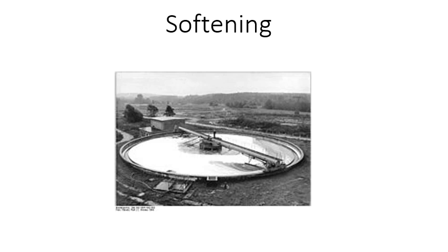For another example, if you have a total alkalinity of 182 milligrams per liter and the total hardness is 223 milligrams per liter, the total alkalinity is less than the total hardness, therefore permanent hardness exists.